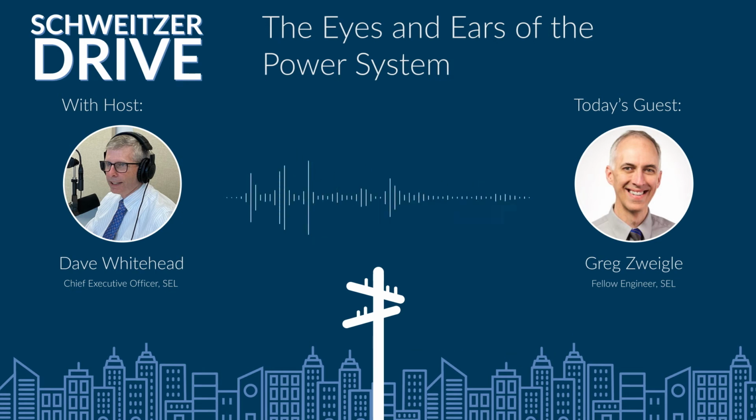If that strobe light is flashing at the frequency, I'm simplifying things a bit, but generally, if it's flashing at the frequency of the power system, like 60 hertz, then the mark will appear exactly each time the strobe light flashes on this shaft. So you'll see that mark appear for every flash of that strobe light, except in a real system, it won't. That mark will appear to slowly wobble back and forth. And that's these really large machines swinging back and forth with respect to each other.